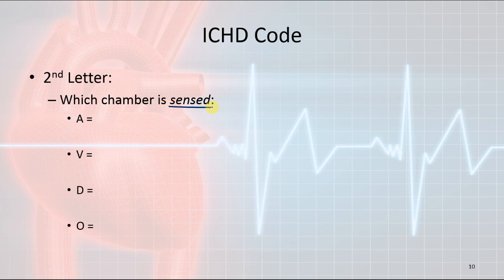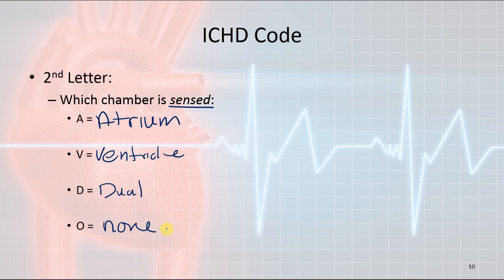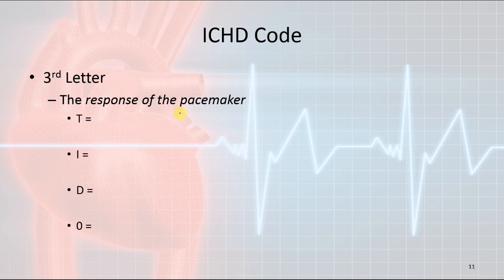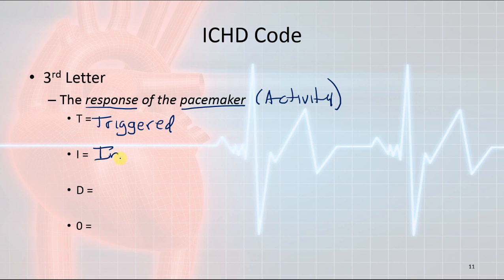The second letter is the chamber that is sensed. A stands once again for atrium. V stands for ventricle. D is for dual. O is for none. The third letter is a little bit more complicated. This is the response of the pacemaker, or as I said earlier, the activity of the pacemaker. I'm going to describe these as we go through them, but I want to list them out first. T stands for triggered. I stands for inhibited. D stands for dual, which means it's both triggered and inhibited, and O is for none.